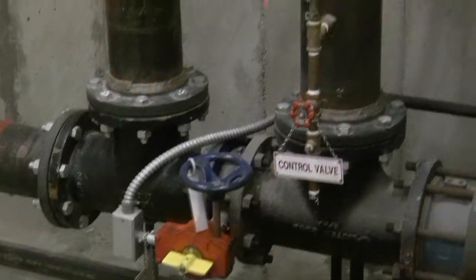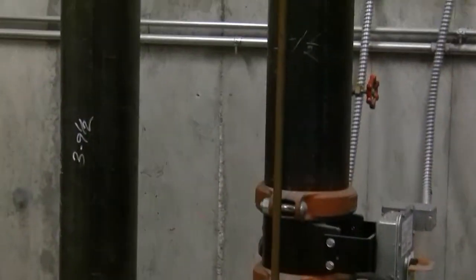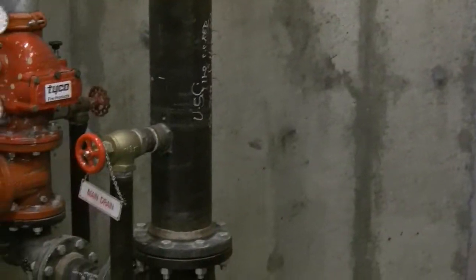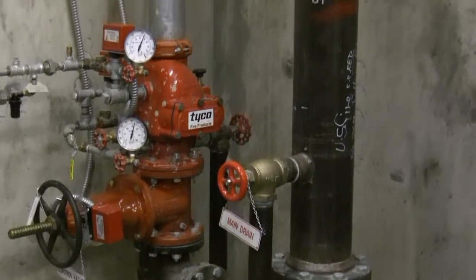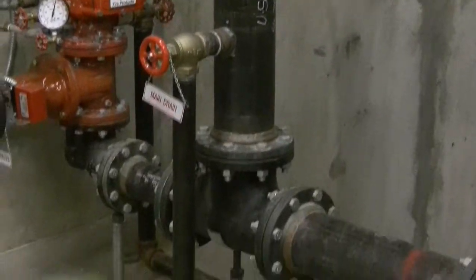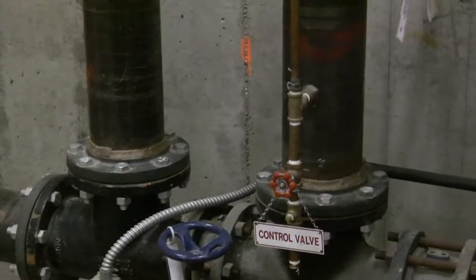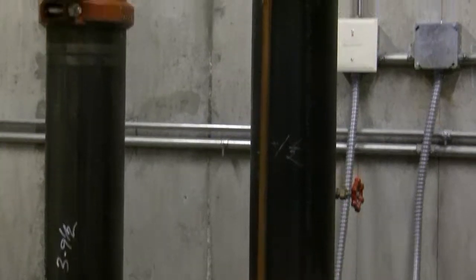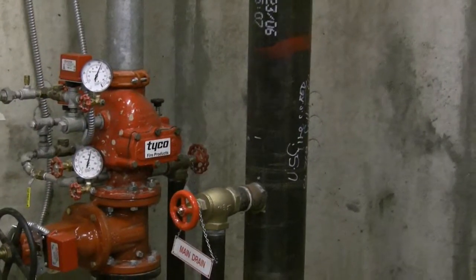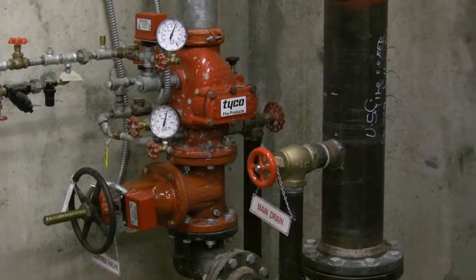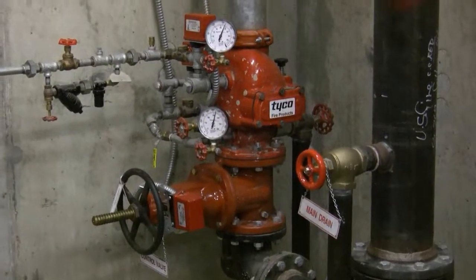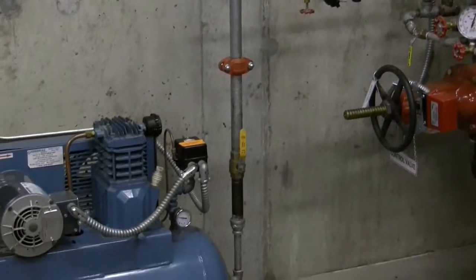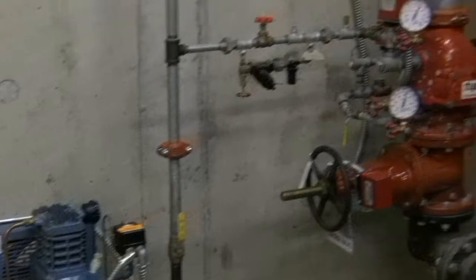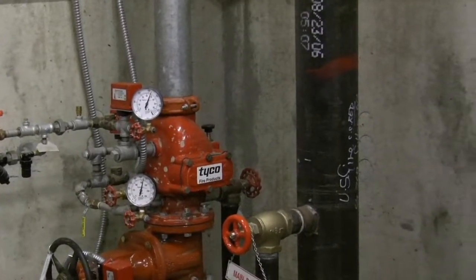There are two types of sprinkler systems in the building. A wet sprinkler system, which is what you'll find in all of the apartments and all of the heated hallways, and a dry system, which is what you'll find in the garage and some areas adjacent to the garage, such as storage areas that might have lower temperature. The dry system is filled with compressed air, and if a sprinkler head is activated, the compressed air is released, and then a large valve will open up and allow water to pass through on a particular floor or zone, depending on how it's laid out. All of the other sprinklers in the building actually have live water in them.